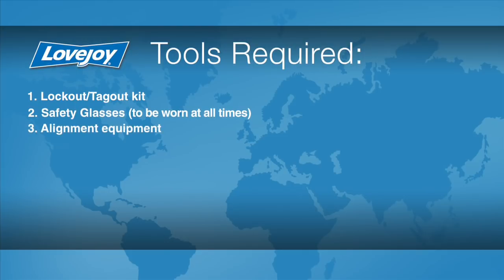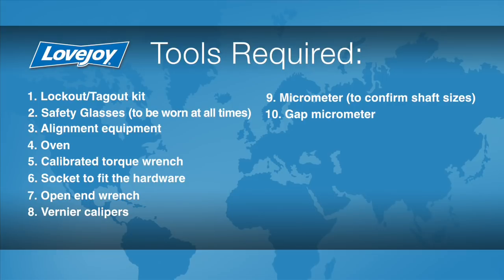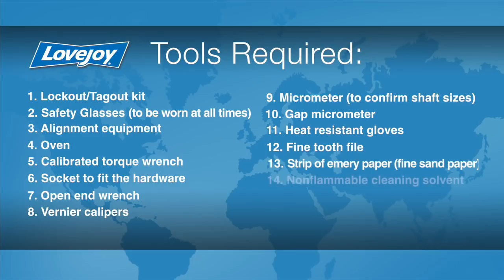Let's look at the necessary tools we will need to perform this installation. A lockout tagout kit, safety glasses, alignment equipment, an oven, calibrated torque wrench, a socket to fit the disc pack lock nuts, an open end wrench, vernier calipers, a micrometer to confirm the shaft sizes, heat resistant gloves, a fine tooth file, a strip of emery paper, non-flammable cleaning solvent, a clean cloth, and rubberized gloves.